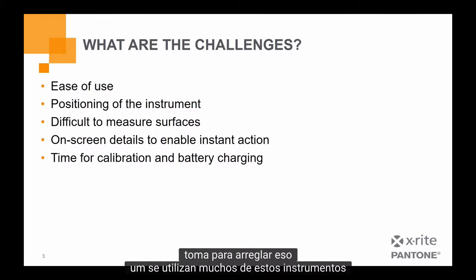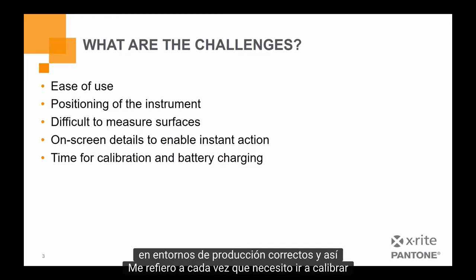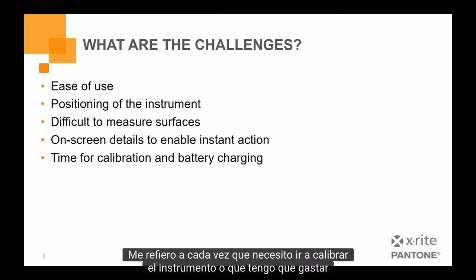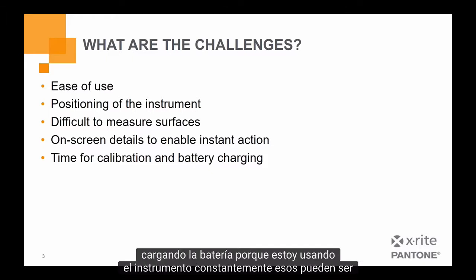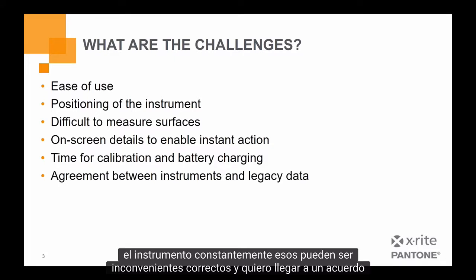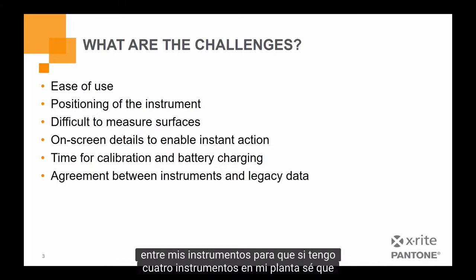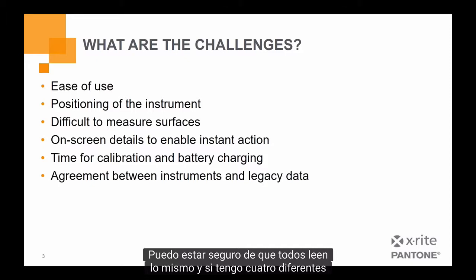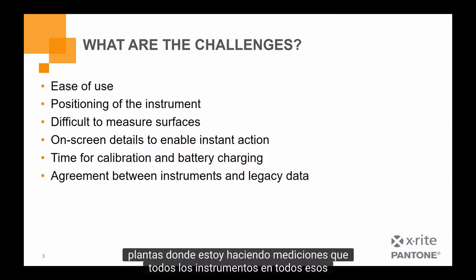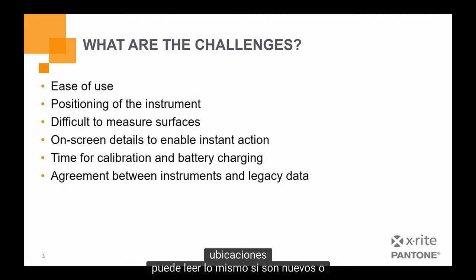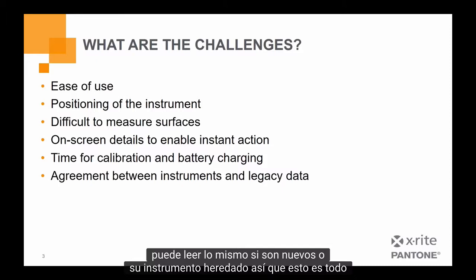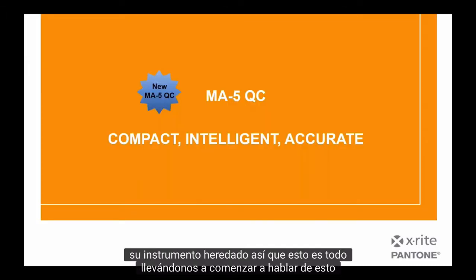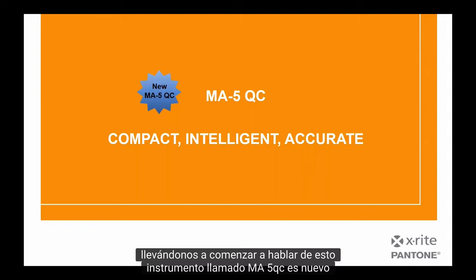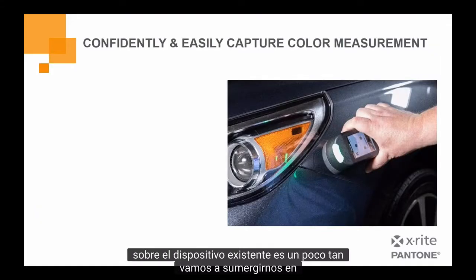A lot of these instruments are used in production environments, right? And so anytime I need to go calibrate the instrument, or have to spend time charging the battery because I'm using the instrument constantly, those can be drawbacks, right? And I want agreement between my instruments, so that if I have 4 instruments in my plant, I can be confident that they all read the same. And if I have 4 different plants where I'm doing measurements, all the instruments in all those locations can read the same, whether they're new or legacy instruments. So this is all leading us to start to talk about this instrument called an MA-5 QC. It's new, it is, but we're also going to talk about the existing devices a bit. So let's dive in.